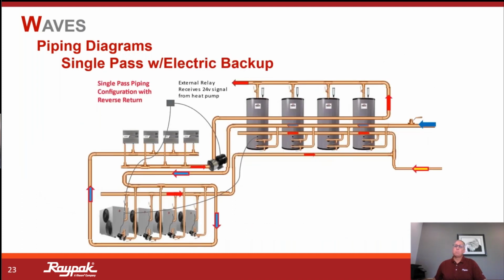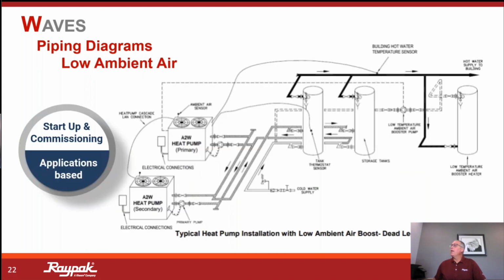Right. Okay. No, I understand that. I was just asking though, in the sequence of operation, as soon as your low ambient tank kicks in, or your gas, whatever you're using for a boost, do the two pumps on the heat pump stop running so it's not continually drawn out of the tank while you're trying to reheat the tank? That would be correct. I'll go back and look at that here because now I have this circulator reloading these tanks, right? So hot coming out, here's my return, reloading the tank with the hottest water until it presumably gets back up to set point in our stored usable hot water.